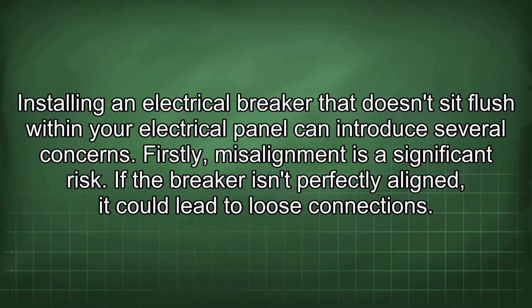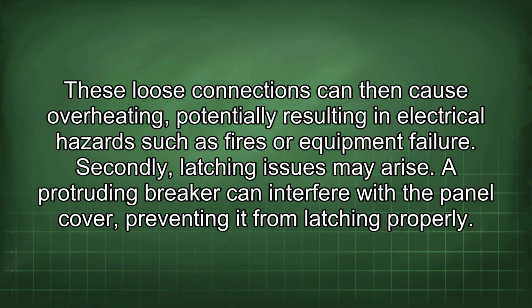Installing an electrical breaker that doesn't sit flush within your electrical panel can introduce several concerns. Firstly, misalignment is a significant risk. If the breaker isn't perfectly aligned, it could lead to loose connections. These loose connections can then cause overheating, potentially resulting in electrical hazards such as fires or equipment failure.